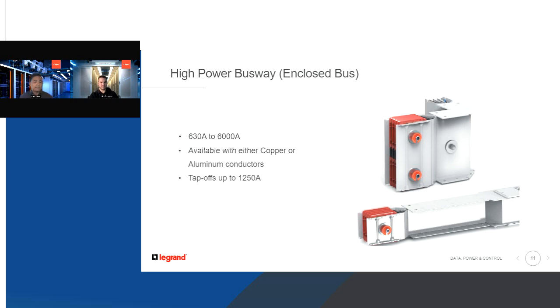I wanted to expose the audience to this because we do have available high power bus. It's an enclosed bus, intended both for the gray space and the white space. So if you're seeing power demand well above 1200 amp, we can still satisfy that request with our high power busway enclosed bus. This line goes all the way up to 6,000 amps and has tap offs all the way up to 1,250 amps.